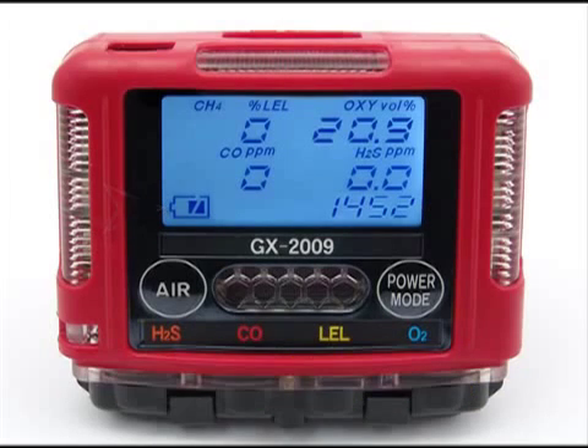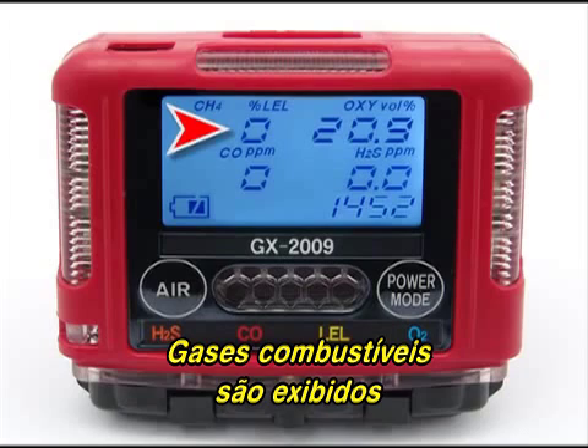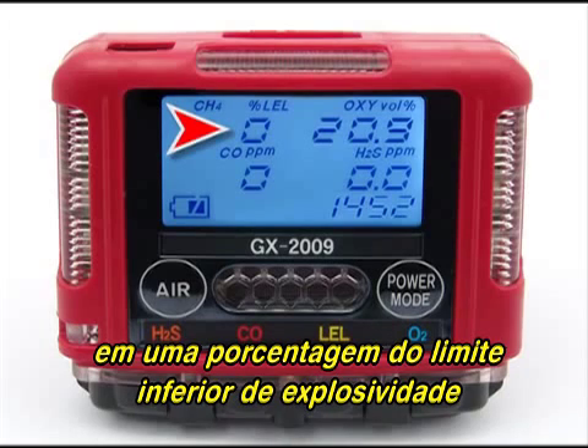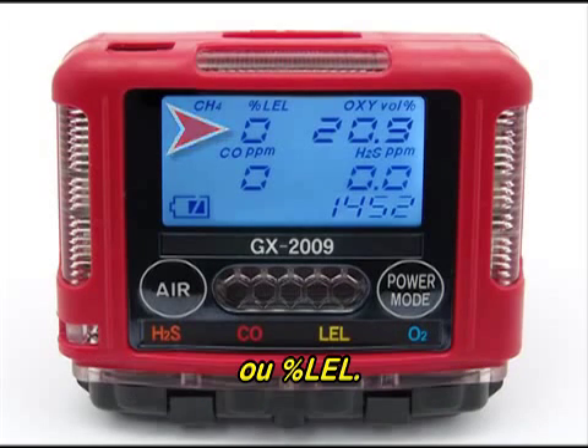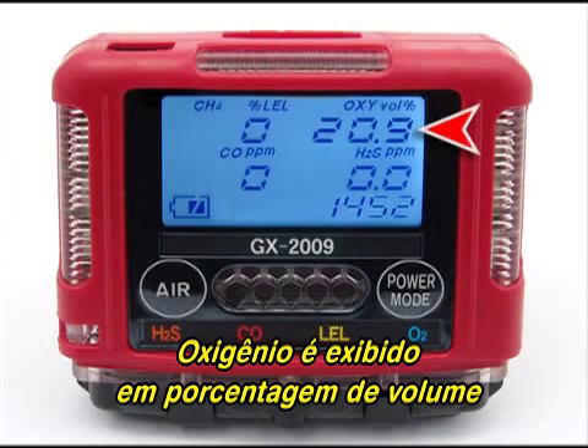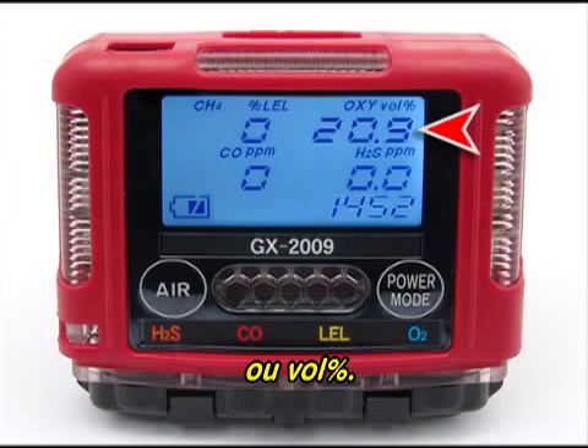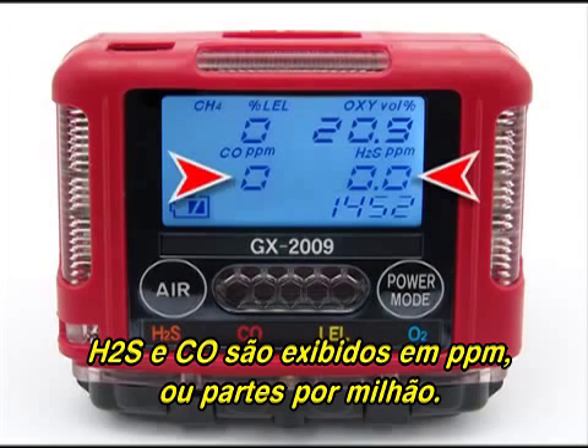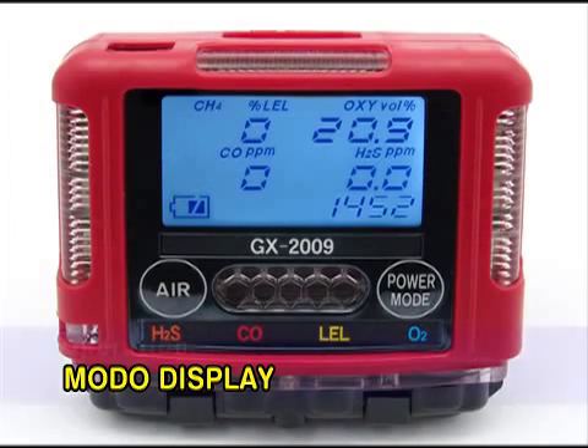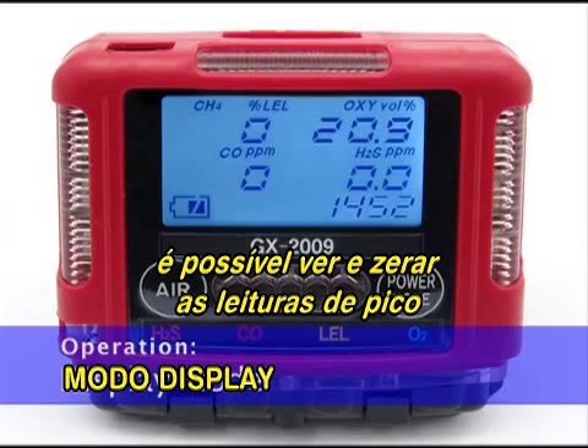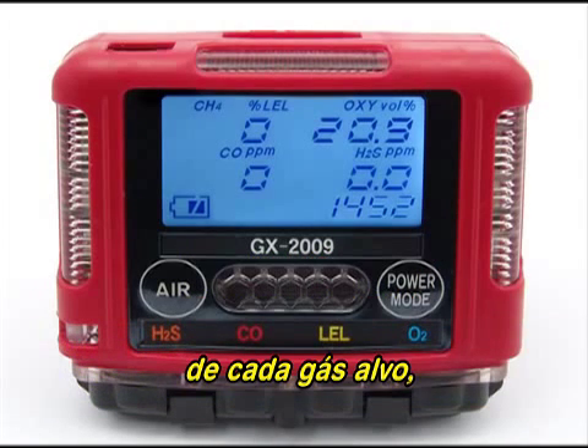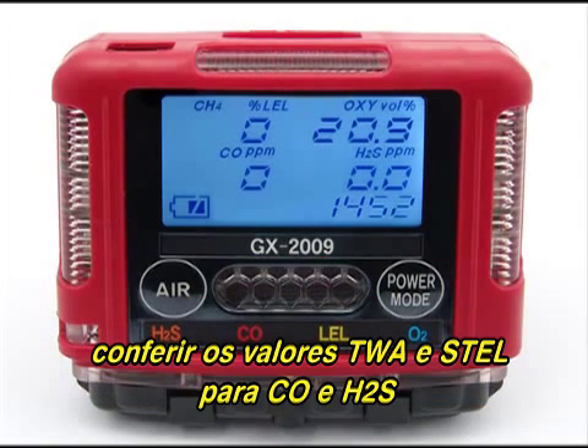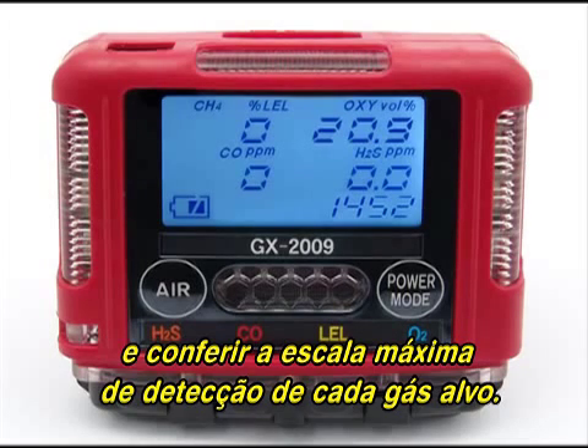corner. Combustible gas is displayed as a percentage of the lower explosive limit, %LEL. Oxygen is displayed as a volume percentage, vol percent, H2S and CO as parts per million, ppm. In display mode, you can view and reset the peak readings for each target gas, view the TWA and STEL values for CO and H2S, and view the detection range full scale for each target gas.